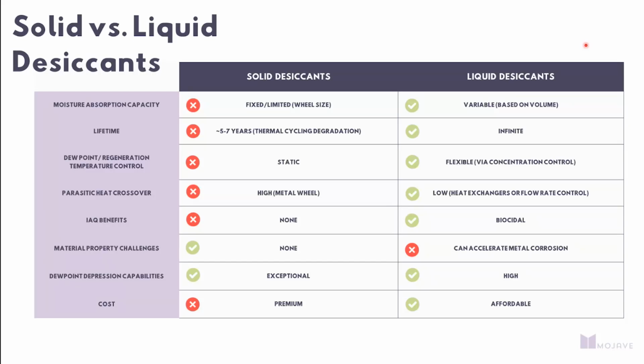One of the key benefits of liquid desiccants over solid desiccants is the regeneration and temperature control. With solid desiccants being a fixed media, it is static. So regardless of whether it's a peak operation or a part load operation, that desiccant wheel is pretty much going to do the same thing every time. There's very little flexibility in how to manipulate its dehumidification capabilities. With a few asterisks on that, which I won't go into, but I'd say reach out to me after the fact and we could discuss if you'd like to.